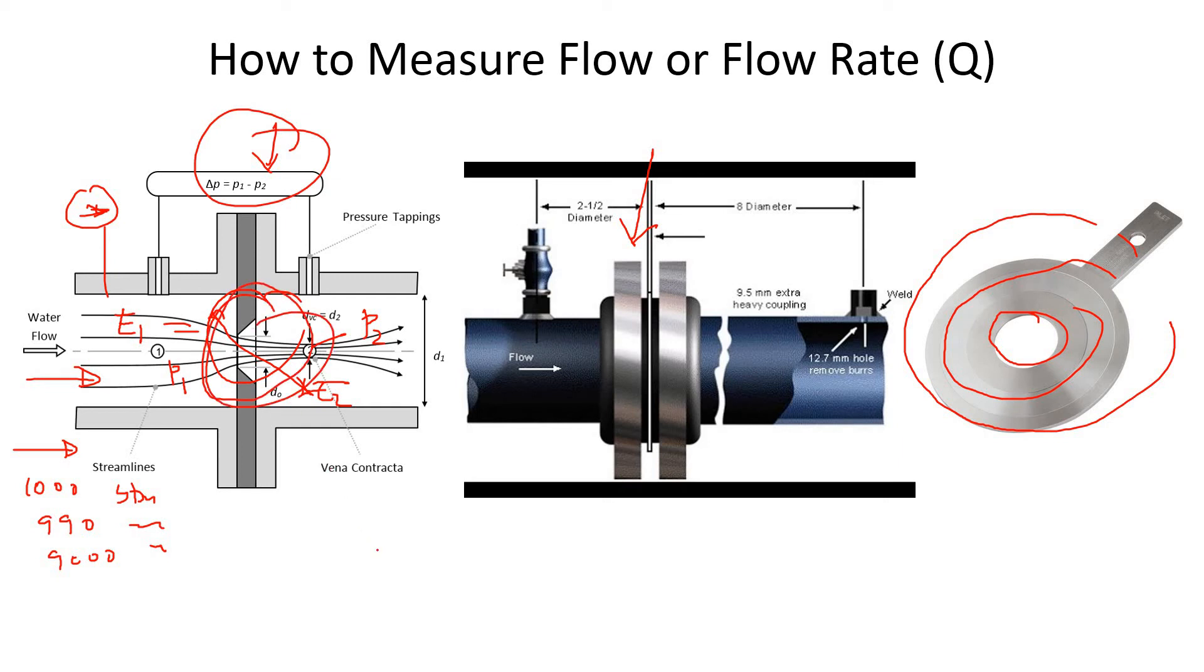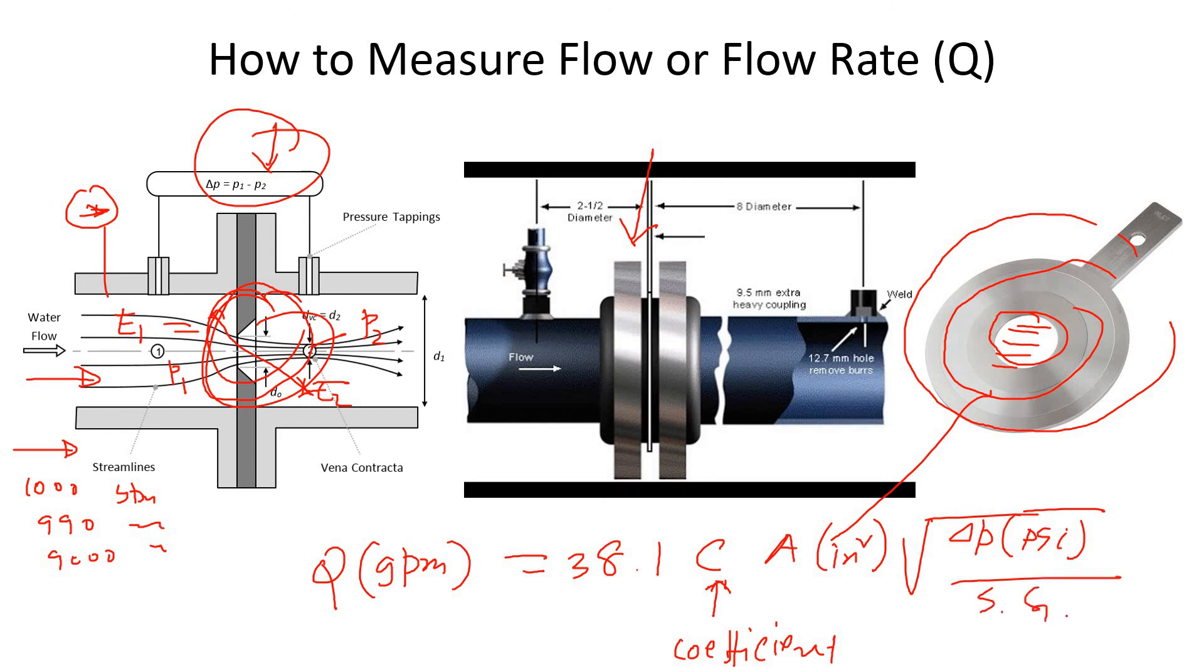If you look at the equation in US units, gallons per minute equals 38.1 times C (the orifice coefficient, which is calibrated using standard flow rates), times the area of the hole in square inches, times the square root of pressure difference in psi, divided by specific gravity. You can use this equation to calculate the flow. All you need is to measure the pressure difference, because the area is standard and the orifice coefficient and diameter are given on the orifice.